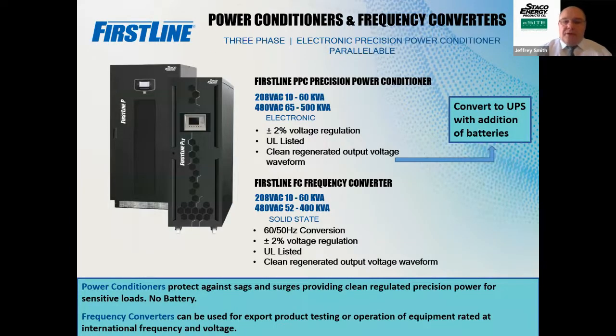When we're going through the power conditioners, the electronic power conditioners, we're able to do this very quickly. Basically, it is a UPS system. As you can see here, it's the same as what we've shown before. It's the UPS, but without batteries. And the unit is able to do this without batteries. We're able to take a higher voltage and even down to lower voltages without batteries and still keep the power up and running. We can go down to as low as 40% on the input and still keep the regulated output. Next slide.